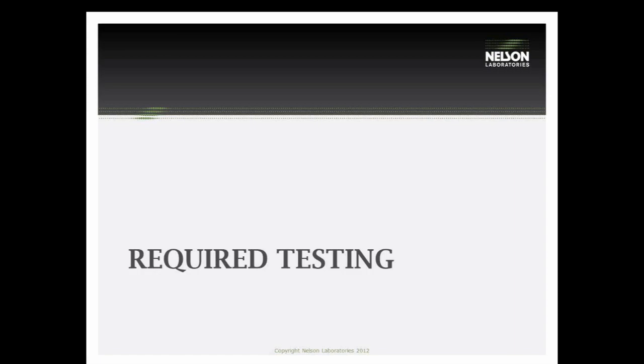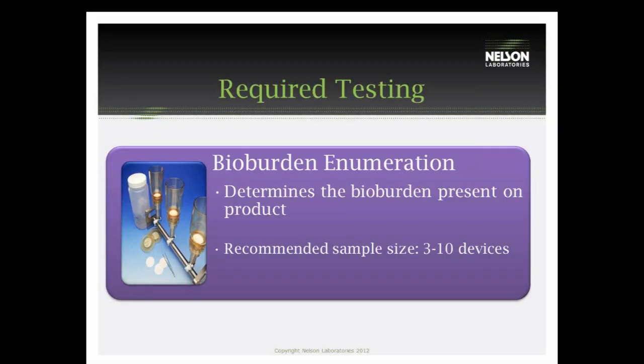There is a lot of required testing, and we'll go over that now and when that testing is to take place. Prior to the half cycle, we will run bioburden enumeration. That testing is going to classify and give us numbers for the bioburden that's present on the device prior to sterilization. This information is important to make sure that we have a cycle adequate to kill the natural bioburden during the half cycle.